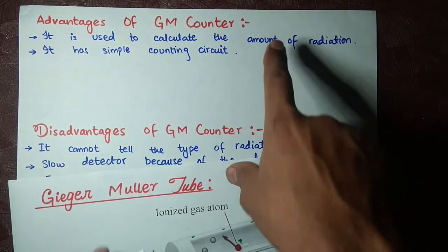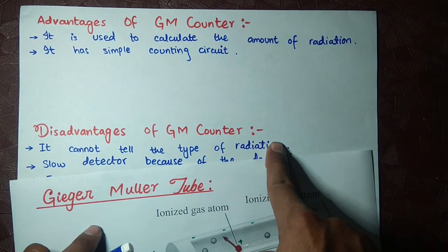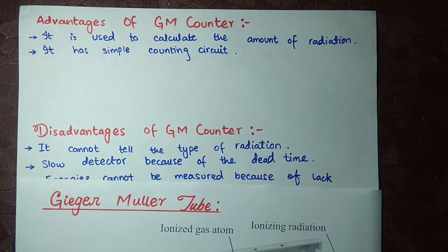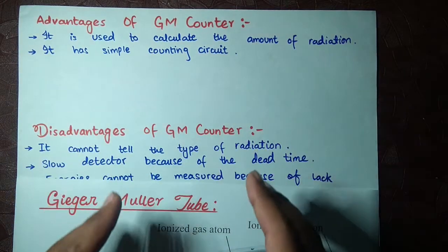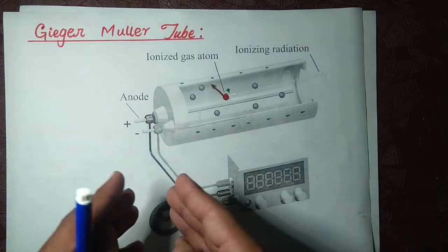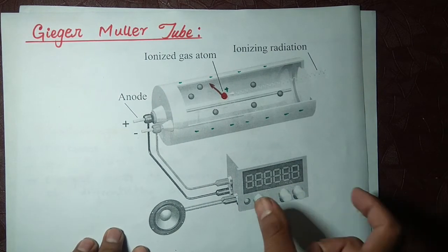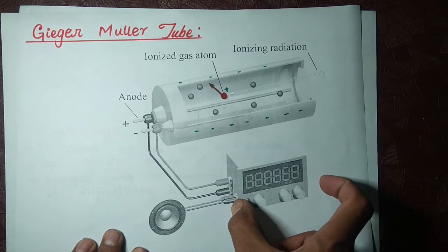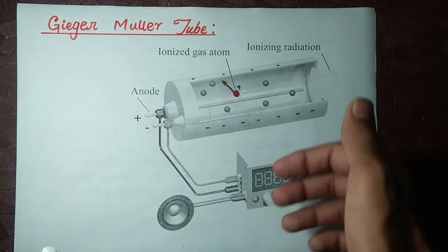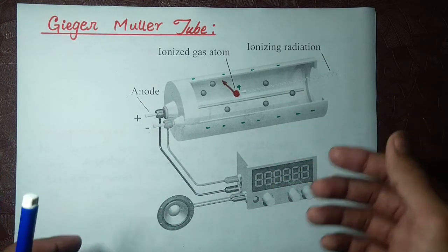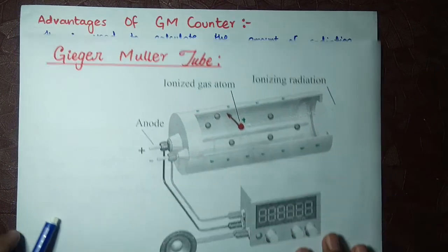So we can calculate the amount of radiation but not the type. Another main advantage of the GM counter is that it has a simple counting circuit. It is not very complicated; its interface is so simple — you can reset with a button, change the scale, and easily read the number of radiation events.